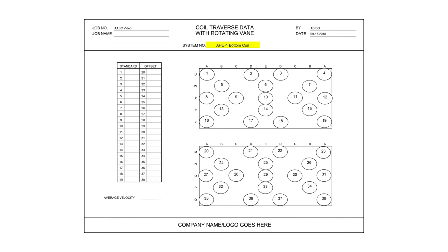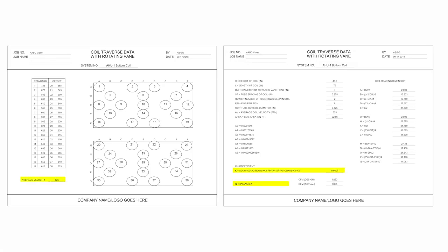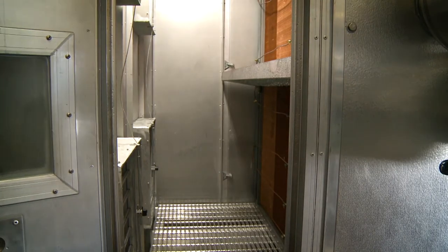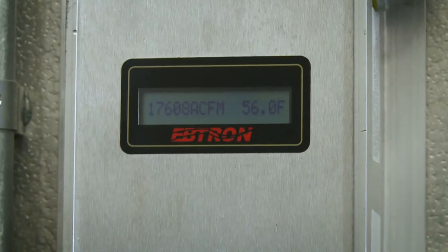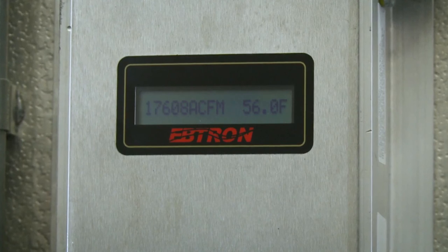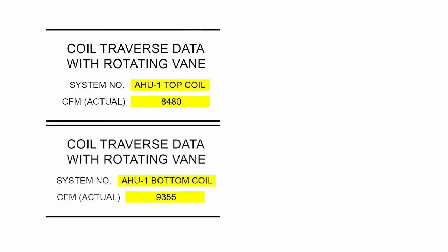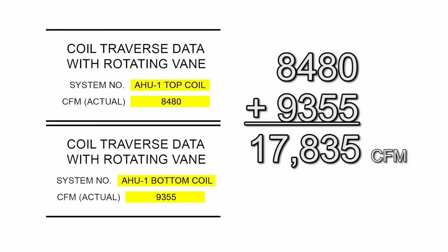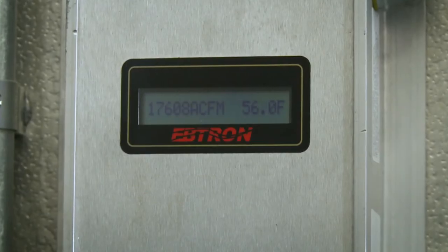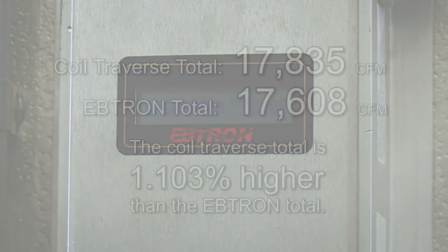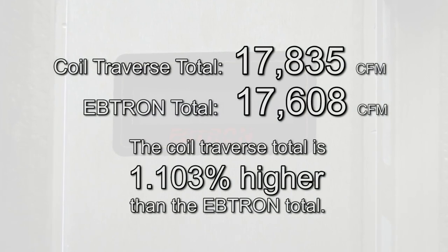On page 2 of the coil traverse data with rotating vane form for AHU-1 Bottom Coil, record the standard velocity readings. The average velocity, K-factor, and CFM actual values are automatically calculated for AHU-1 Bottom Coil. Each of the four fan inlets has a flow station, which is totalized to give the actual airflow. The Ebtron flow station's actual airflow for both top and bottom unit totalized is 17,608 CFM. The AHU-1 Top Coil actual CFM is 8,480, and the AHU-1 Bottom Coil actual CFM is 9,355, with a total of 17,835 CFM. Therefore, the coil traverse total is 1.103% higher than the Ebtron total.